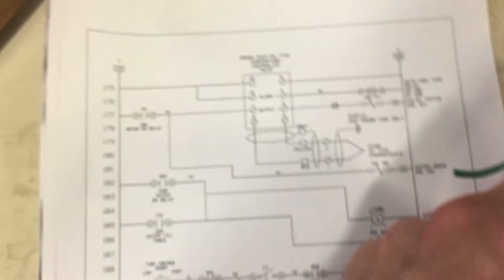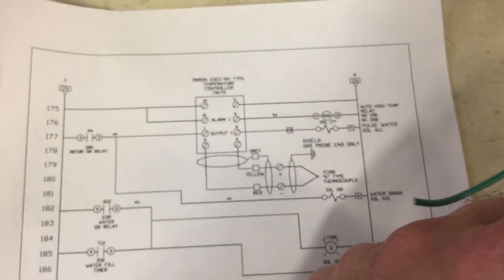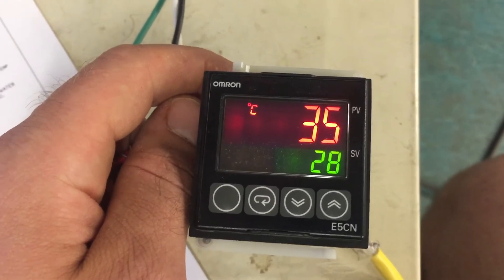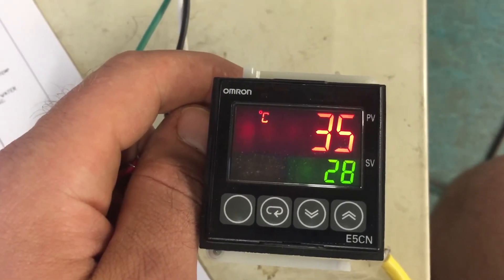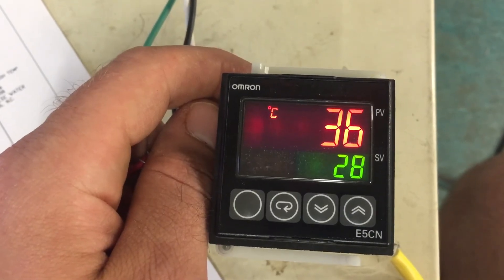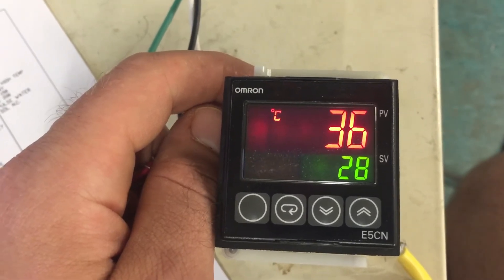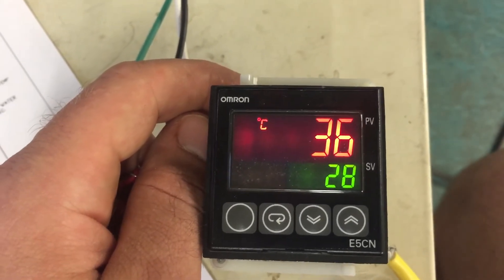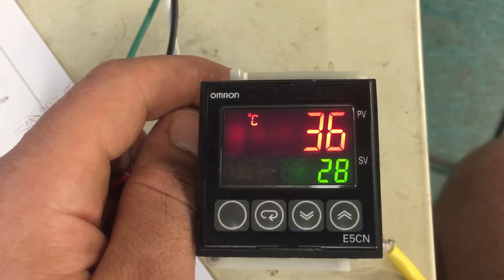And eventually you see the output one clicking on and off. So as I mentioned with our electrical, output one is connected to the pulse water solenoid. What happens is based on a PID function on how this is reacting, it will designate the output one to start giving it controlled bursts of water. If it's cycled up and continues to rise quickly, that output will activate for longer pulse periods. Now, my temperature is increasing because my thumb is quite hot. You see that output one is starting to increase because it's not getting a reaction out of the temperature. It will continue to increase the output length just like it is if there's no reaction in that process value.